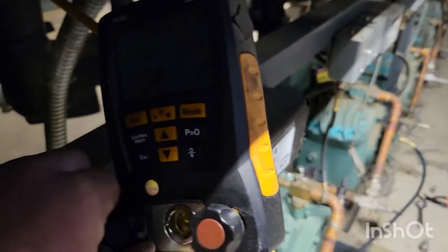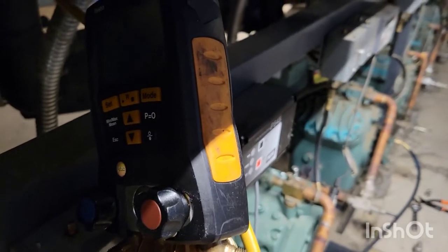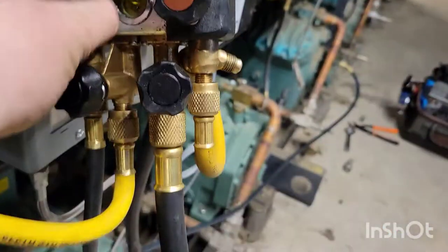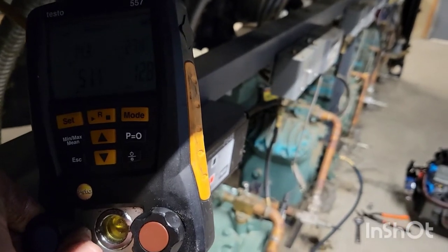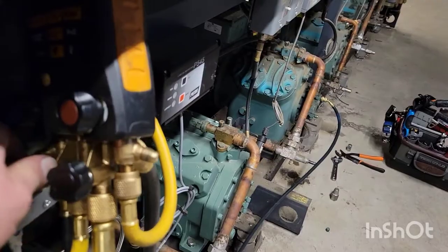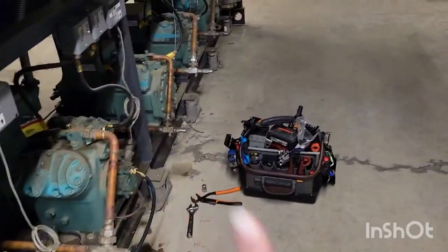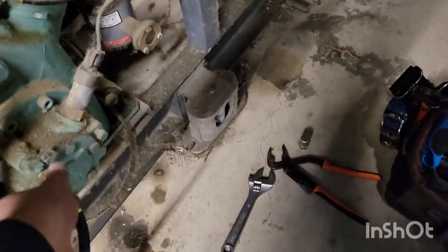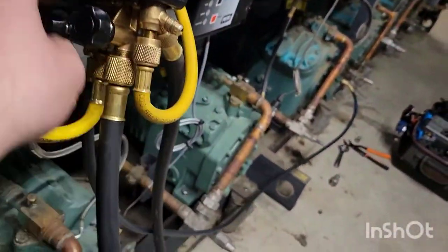We'll see that with that compressor running we have 50 PSI on that side on the gauge, and on the other side of the gauge hooked up to the rack we have 12 PSI. So now I'm opening up my gauges. Remember, high pressure goes to low pressure, so this high pressure oil pump is pushing the oil through here into my gauges, and I've hooked up over here.